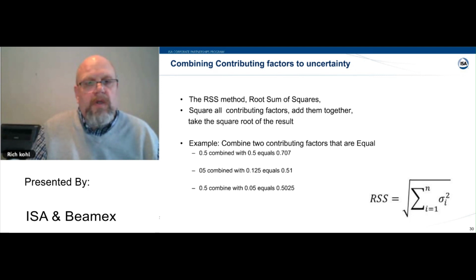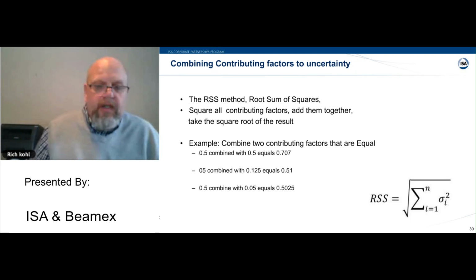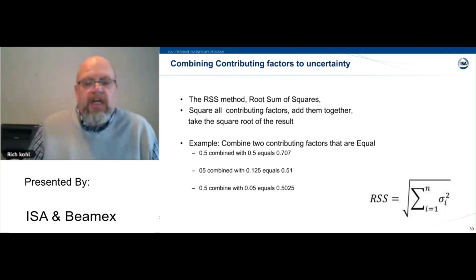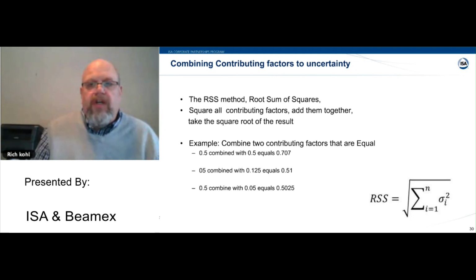So let's see what else. One note is what can you RSS together and what can you not? In the world of calibration uncertainty, there are two kinds of contributing factors. They're called non-correlated and correlated. So the first one, non-correlated, is where the contributing factors are independent of each other and you can RSS them together. How you recognize this on a spec sheet is it'll always be a plus or minus kind of spec, plus or minus 0.05% of scale, for example, right?